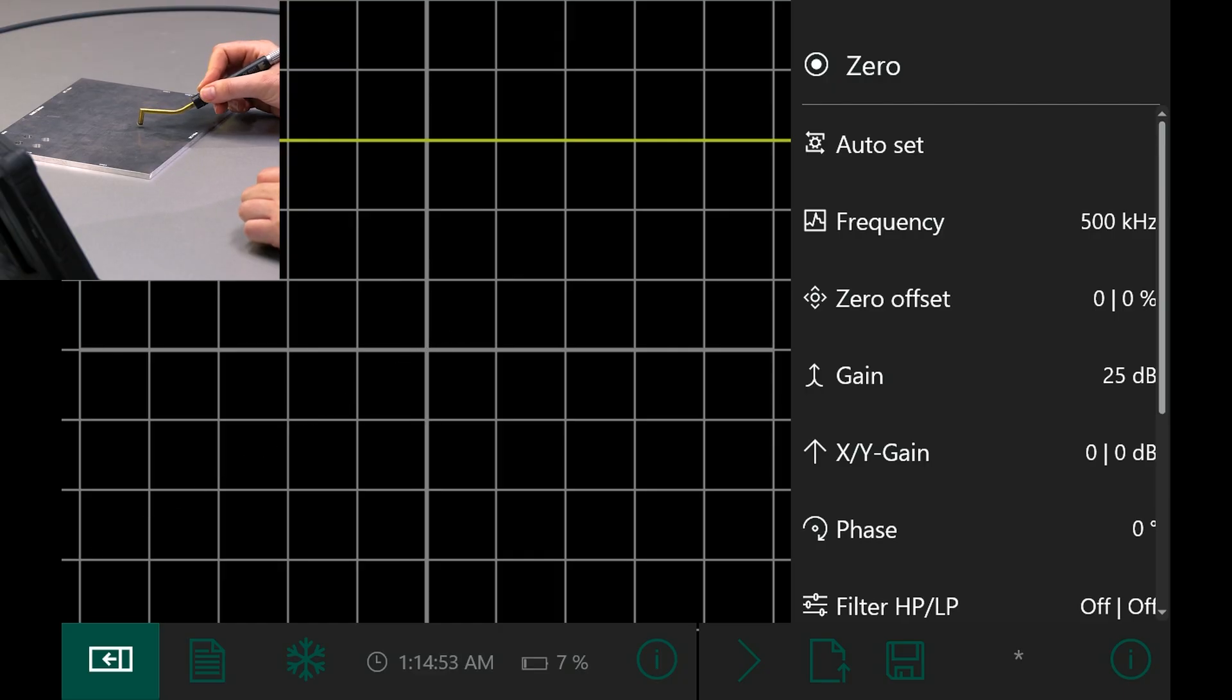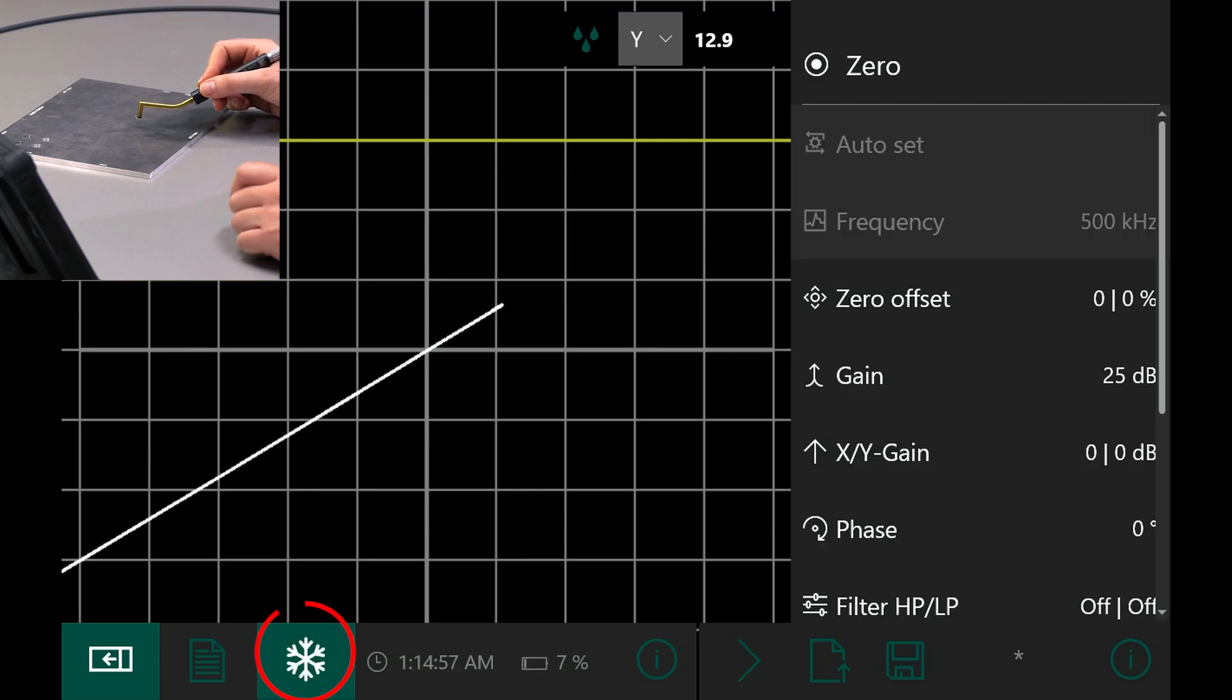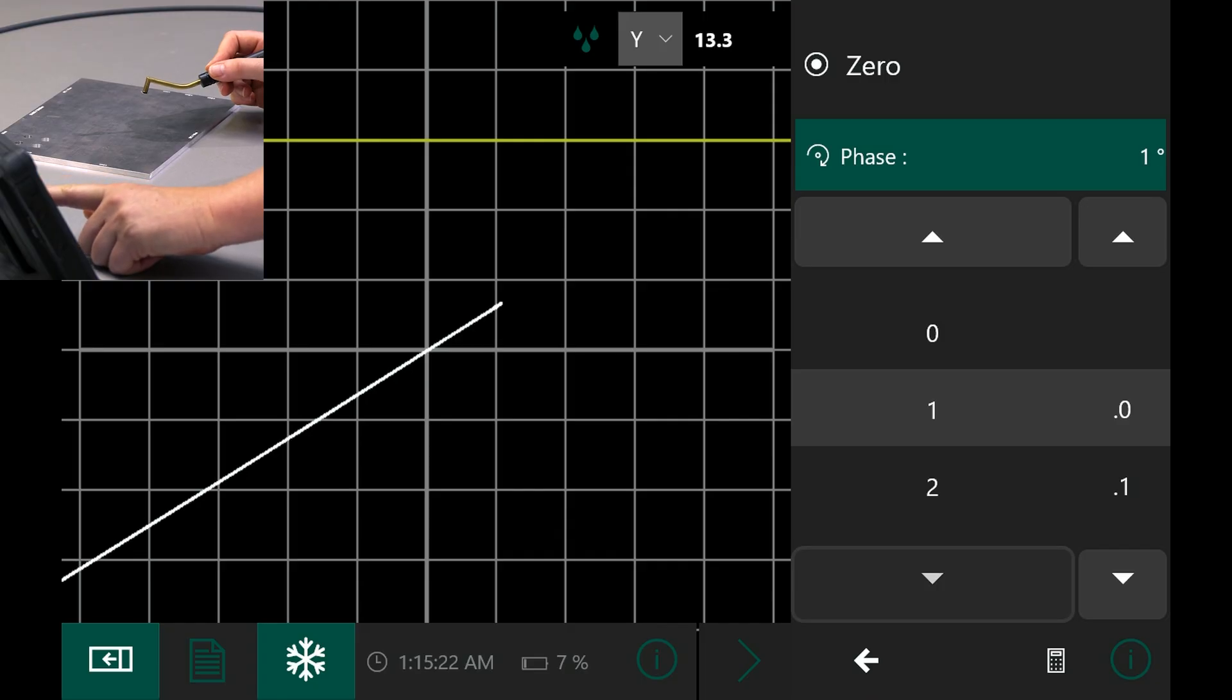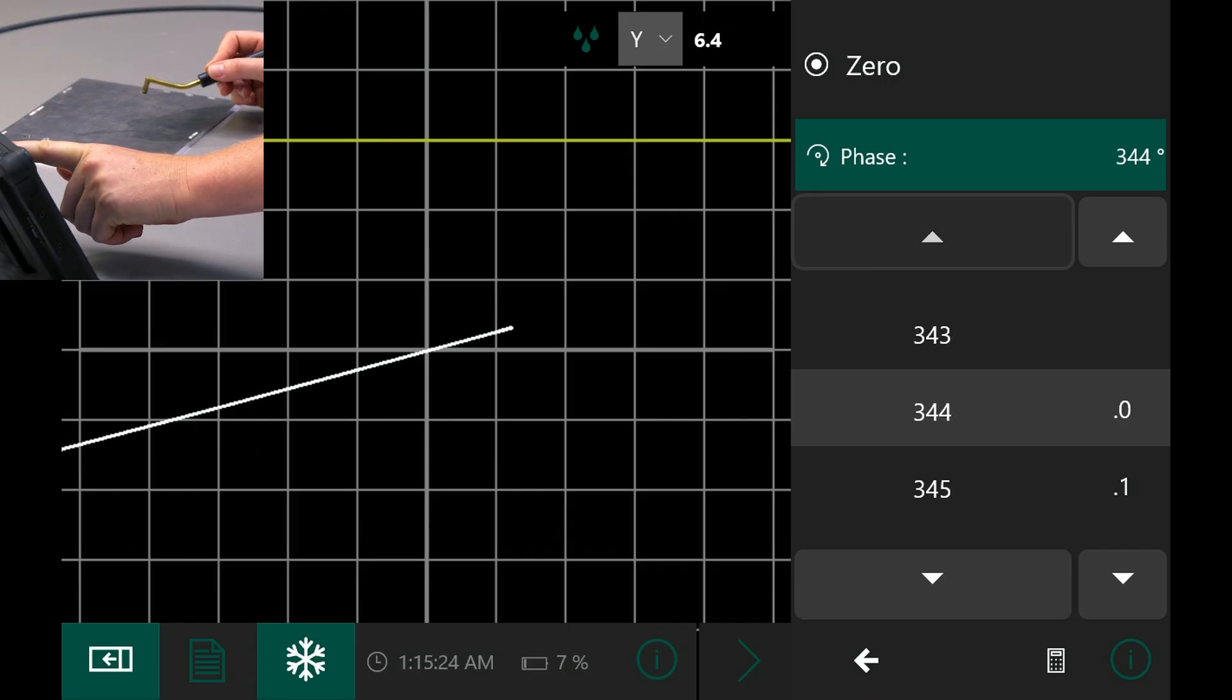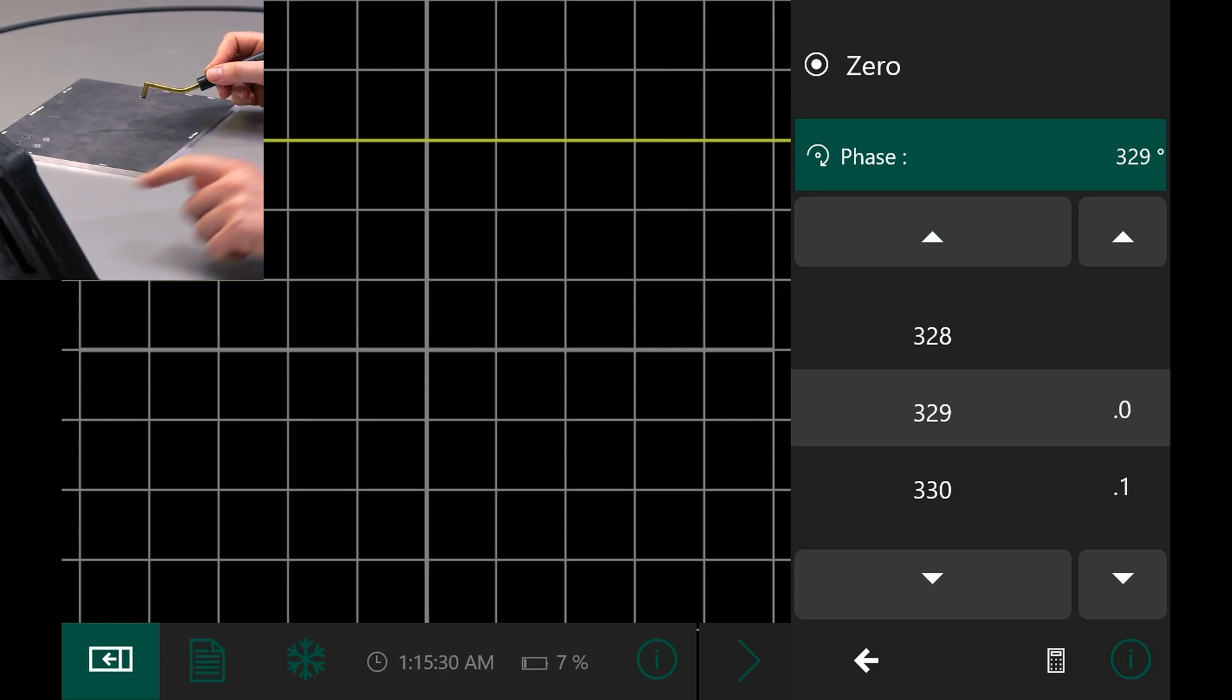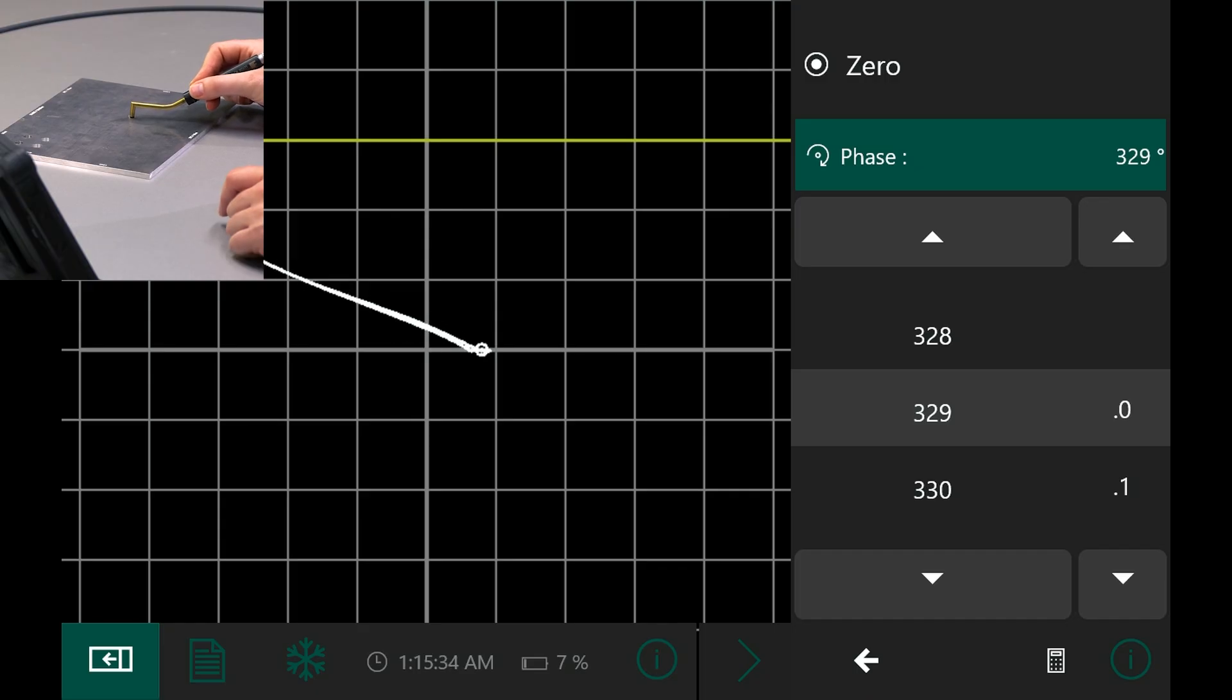I want to position it so that it runs horizontally. To do this, I freeze the screen using the snowflake icon when the liftoff appears. Using phase, I can now move the liftoff so that it runs horizontally. Now the correct signal is in the y-direction. This already looks quite good.